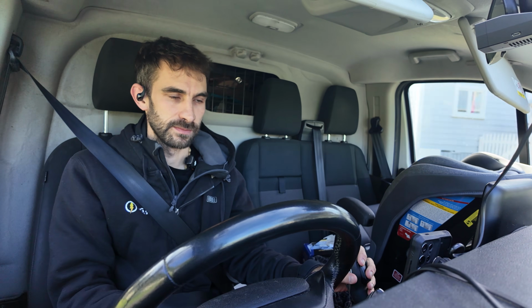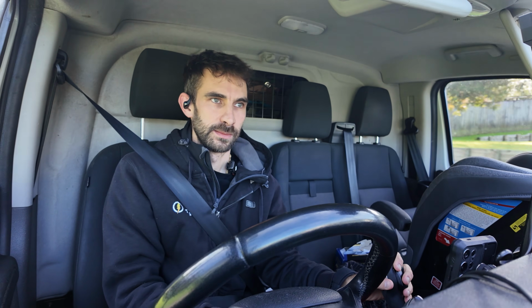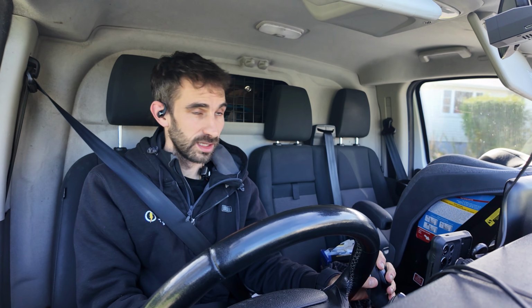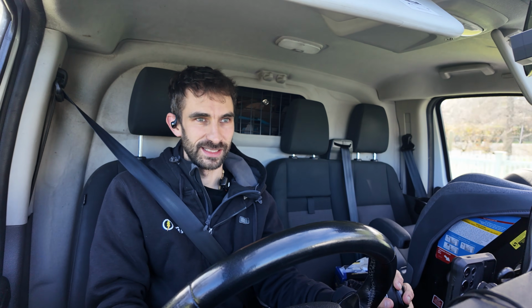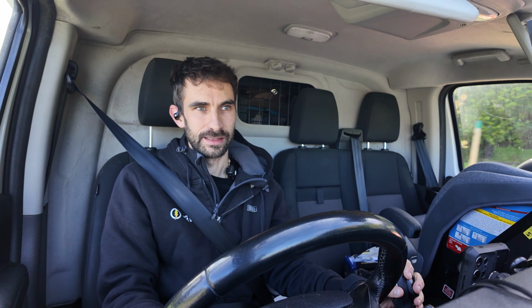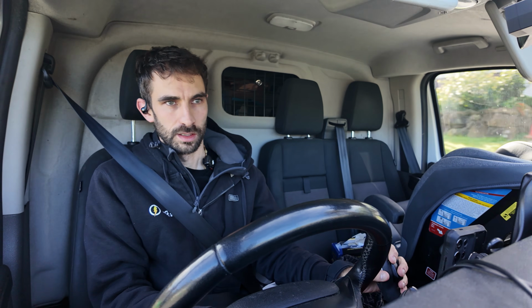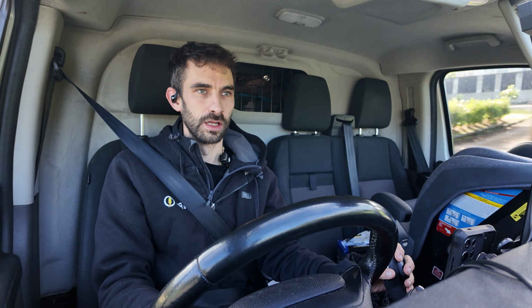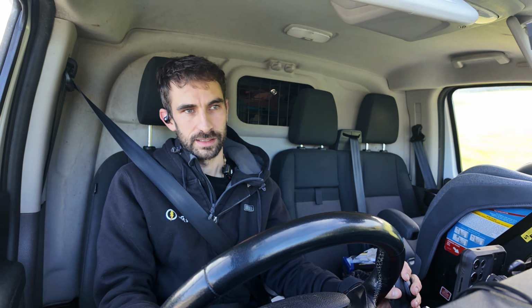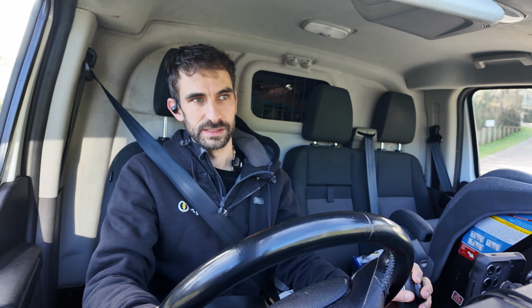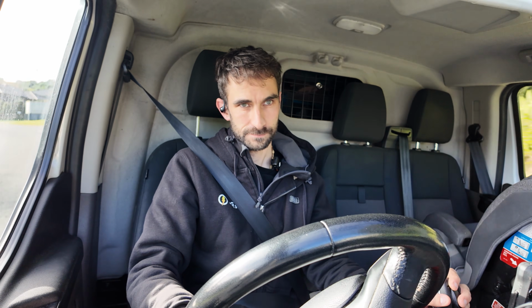There is an earthing system, but it doesn't operate protective devices, because if someone's in the middle of a medical procedure and the power suddenly turns off to a device, the results from that could be catastrophic. So instead of turning the power off, if a fault happens, an alert is sent out so that the doctors and technicians can safely resolve the fault without a sudden power loss. Because it takes 2 faults under that condition for harm to occur, so an alert is enough.